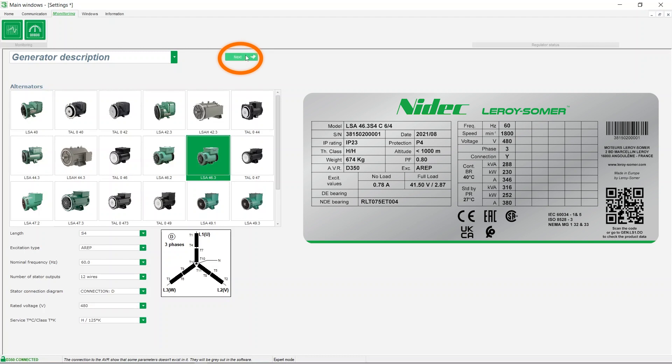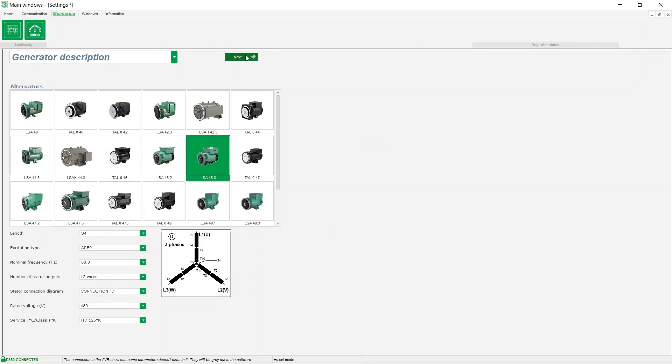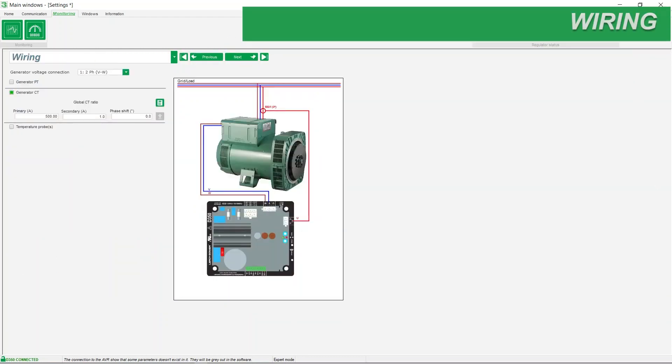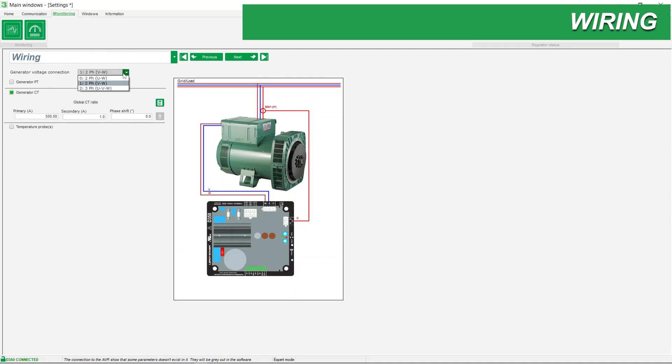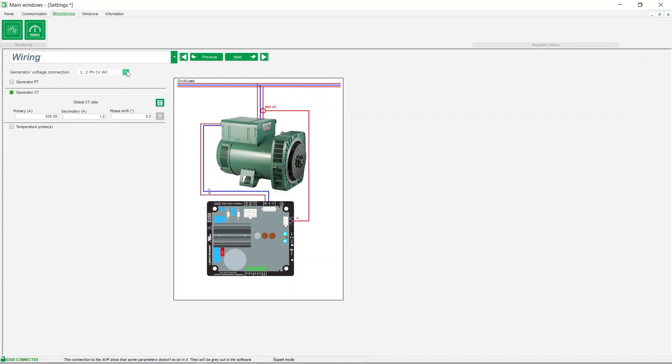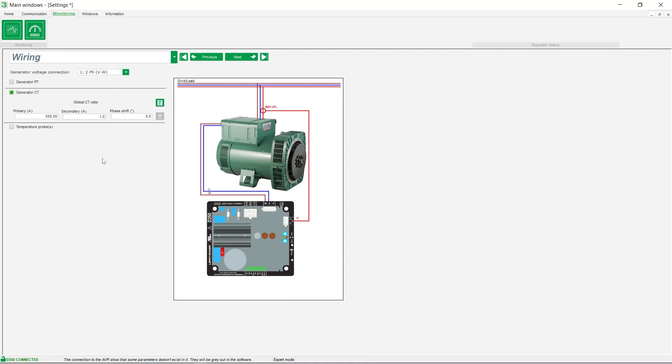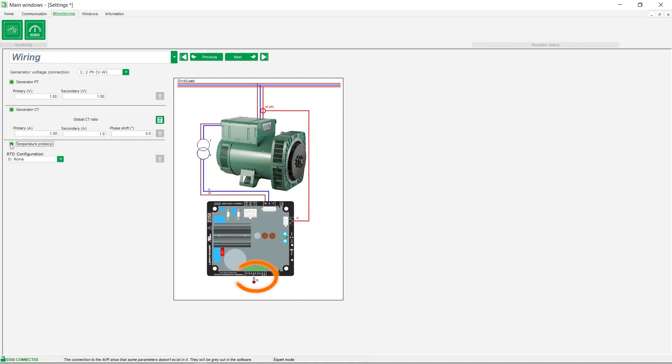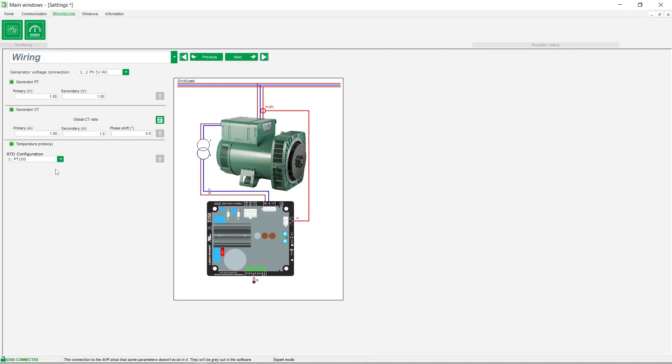Click on next to access the wiring section. The voltage sensing, referred to as generator voltage connection here, depends on the wiring of your alternator. You can configure voltage transformers PT, current transformers CT, or temperature probes here. Enter the values for the transformers or sensors installed on your alternator as needed.